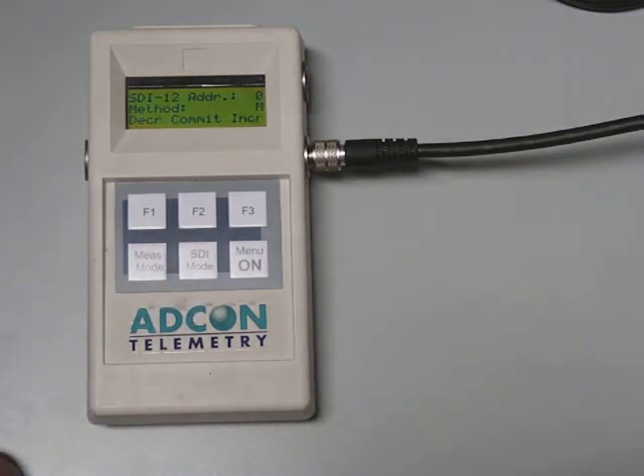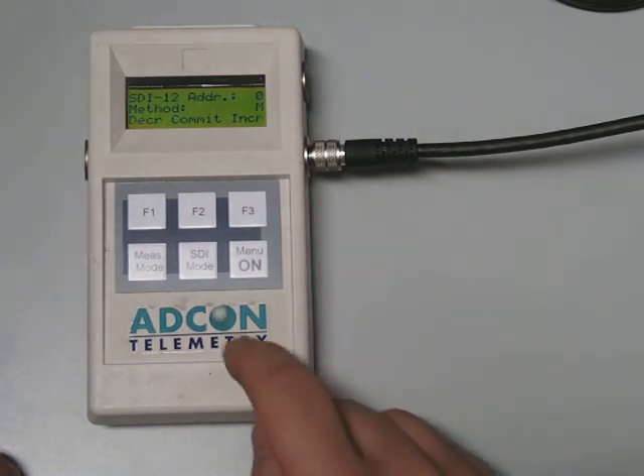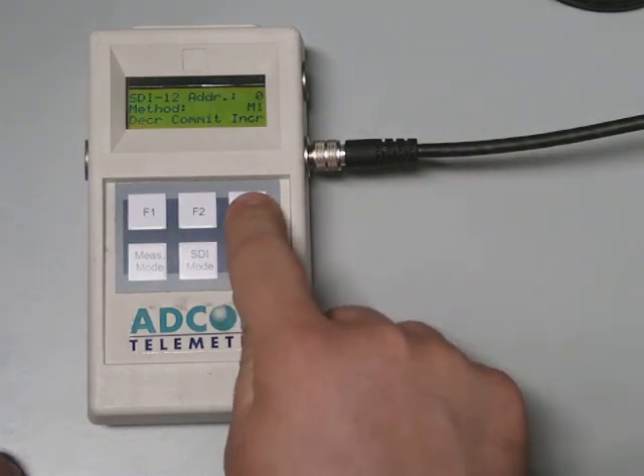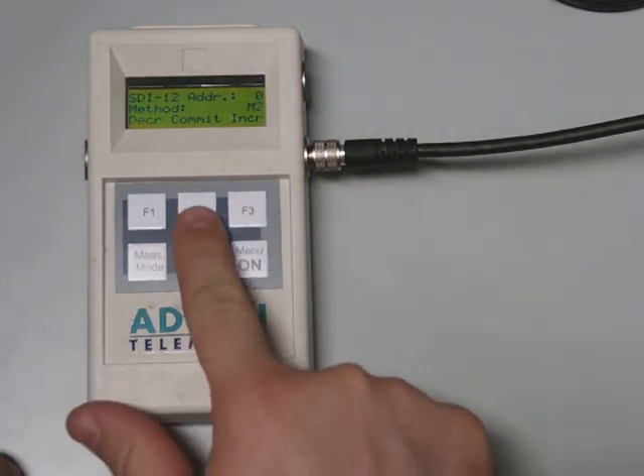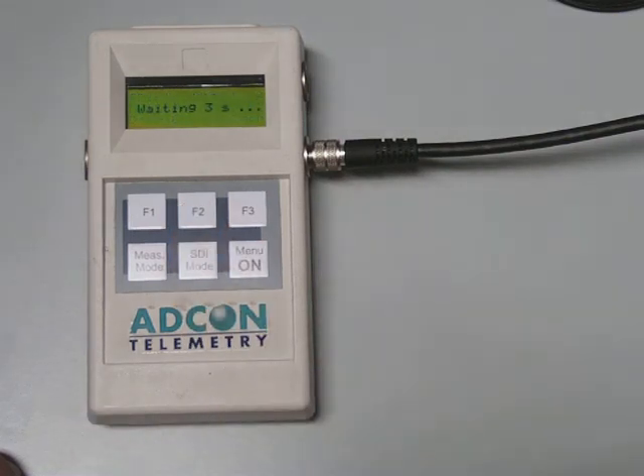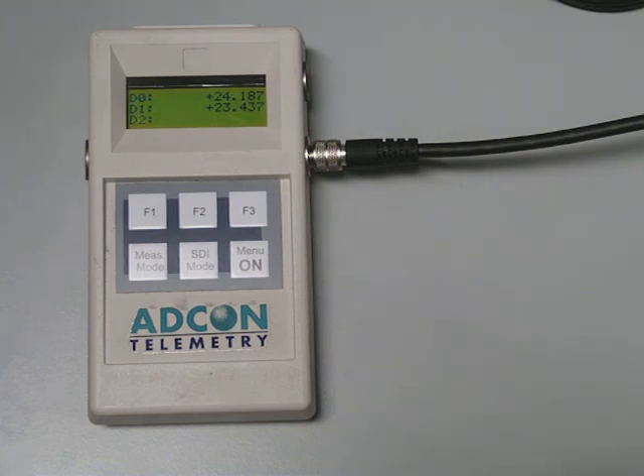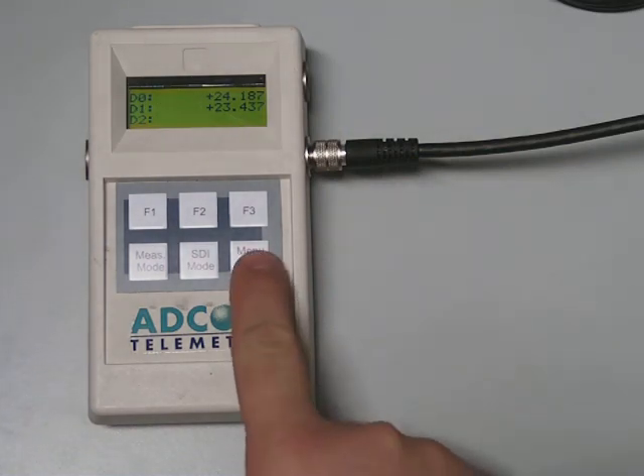We'll press the SDI button another time for a bus scan, and a third time to get to the M command selector. Pushing F3 twice will switch us to method M2, and we commit this command by pressing the F2 key. After a rapid countdown from 3 seconds, we will get 2 temperature values on indices 0 and 1. Having performed all the tasks that we want, we push the On button briefly, and it will switch off our device and our session has ended.